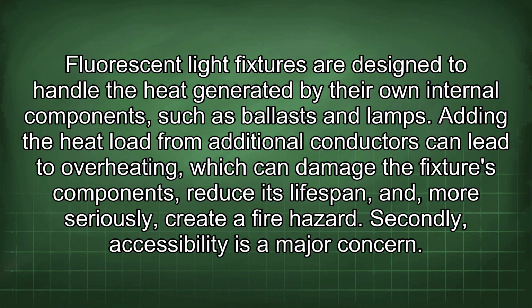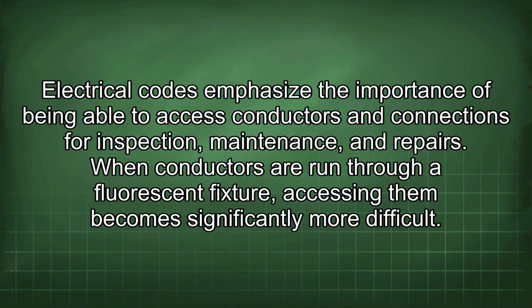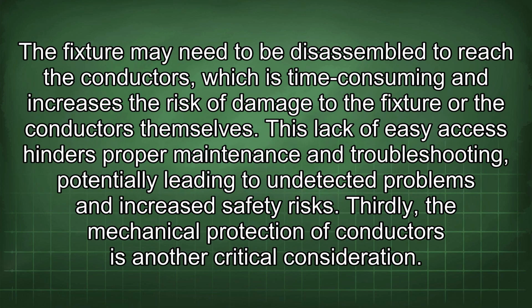Secondly, accessibility is a major concern. Electrical codes emphasize the importance of being able to access conductors and connections for inspection, maintenance, and repairs. When conductors are run through a fluorescent fixture, accessing them becomes significantly more difficult. The fixture may need to be disassembled to reach the conductors, which is time-consuming and increases the risk of damage to the fixture or the conductors themselves. This lack of easy access hinders proper maintenance and troubleshooting, potentially leading to undetected problems and increased safety risks.